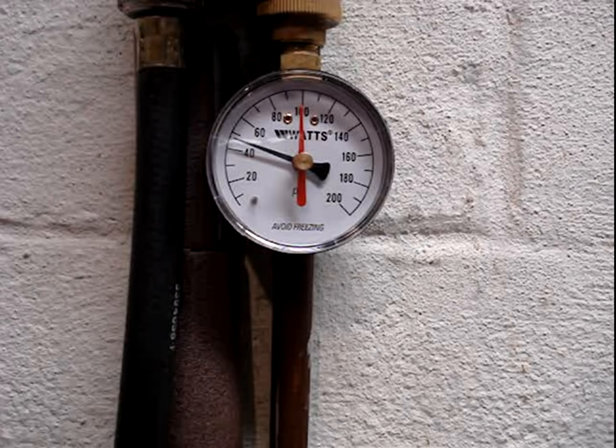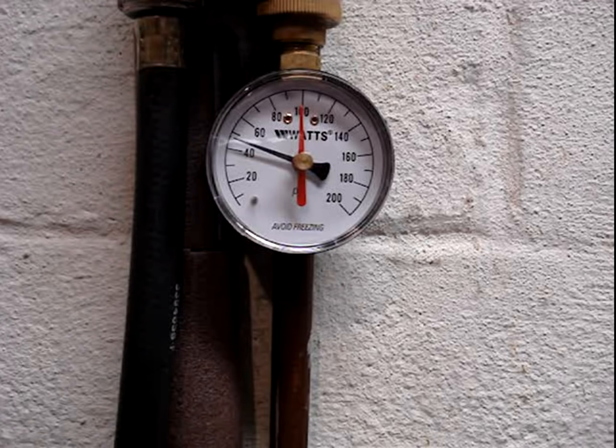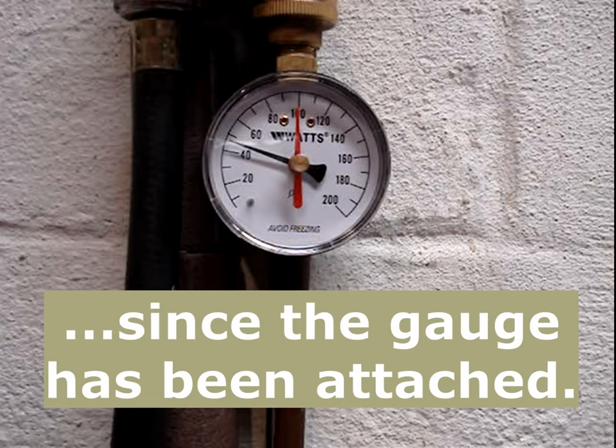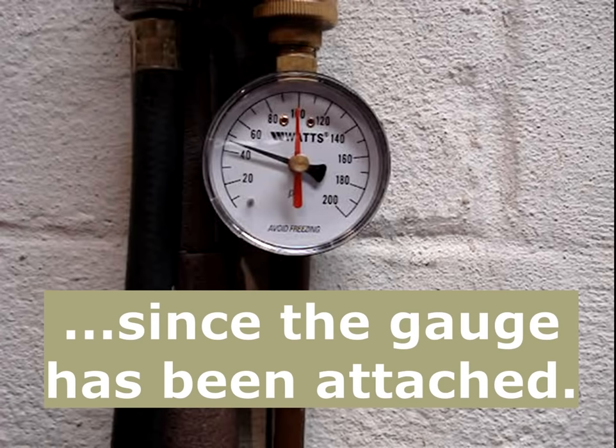The municipal pressure is normally about 90 pounds, and it's being reduced to around 50 pounds by the water pressure reducing valve. Ten minutes has passed, and the water pressure is staying steady, just a little bit below 50 pounds.